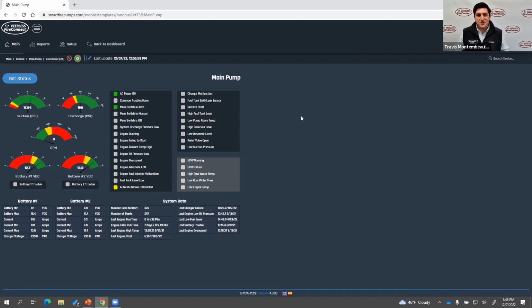So that NFPA 25 checklist, it was on the PowerPoint, but I wanted to get to the demo, we show that weekly checklist that's 2 pages. And already over 50% of those items on that checklist, FireConnect automates. So you get that information without even having to step foot into the pump room. Some of that ear, nose, and eye test stuff is still critical to that checklist, and that's what we're not picking up yet. So adding things like a camera becomes a no-brainer as we're moving forward. And then NFPA will make decisions based on the data they have that says, maybe we don't need to check for that, or actually, we're not checking for this, maybe we need to check this more frequently. So they're becoming a little bit smarter about how they're looking for it.